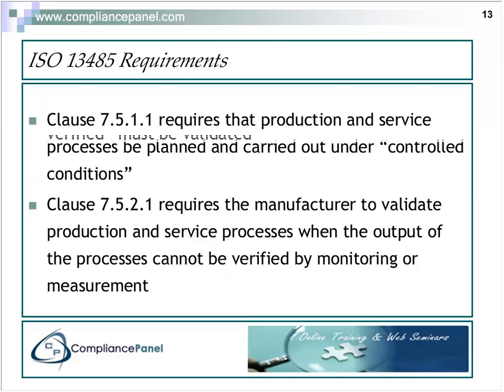Okay, I mentioned that we have other requirements beside FDA. If we look at ISO 13485, which of course is the quality system requirement for many other countries in the world, in Japan that is part of the regulation. It has been translated into law. In Europe, of course, there's a harmonized standard there, and if you choose to use it, you must comply with that harmonized standard. In Canada, you're required to use 13485, and there's other countries in the world that do refer to this particular standard.